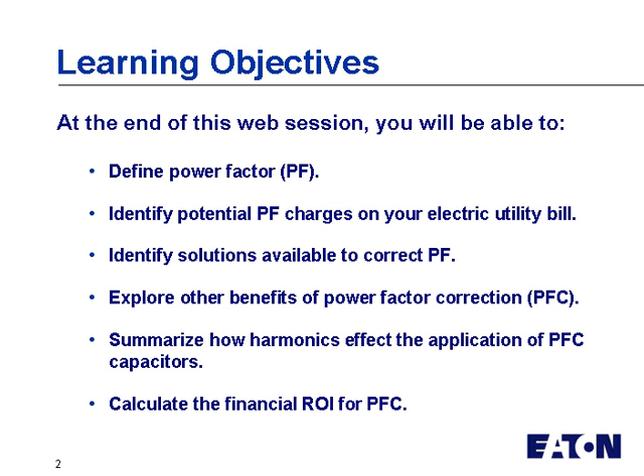Thirdly, we'd like to identify solutions available to correct power factor. Then we'd like to explore other benefits of power factor correction. There are some reasonable other benefits that aren't necessarily going to show an ROI directly, but we'll tell you what those are, and there are other reasons why you would install power factor correction. Additionally, we'd like to summarize how harmonics affect the application of power factor correction capacitors, because that's an important issue today. And finally, one of the main reasons we pulled everybody together today was, of course, to calculate the return on investment for power factor correction.